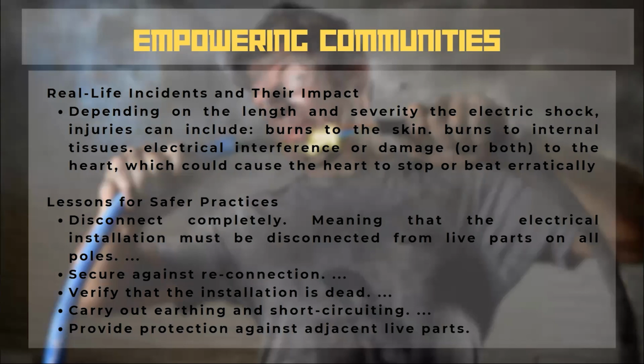First is to disconnect completely, meaning the electrical installation must be disconnected from live parts on all poles. Second is to secure against reconnection. Third, verify that the installation is dead. Fourth, carry out earthing and short circuiting. Last is to provide protection against adjacent live parts.